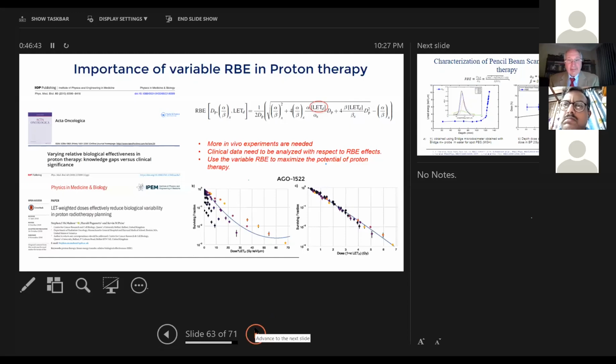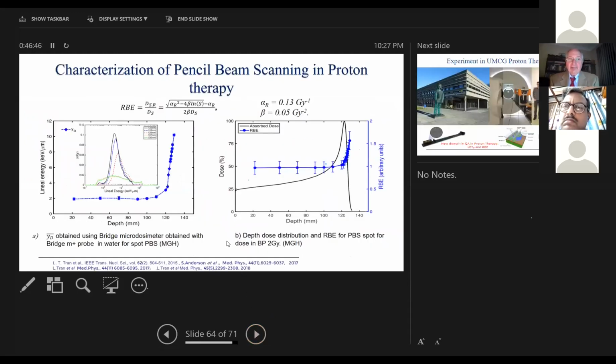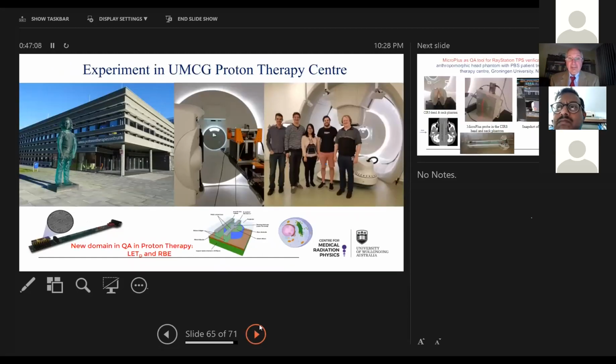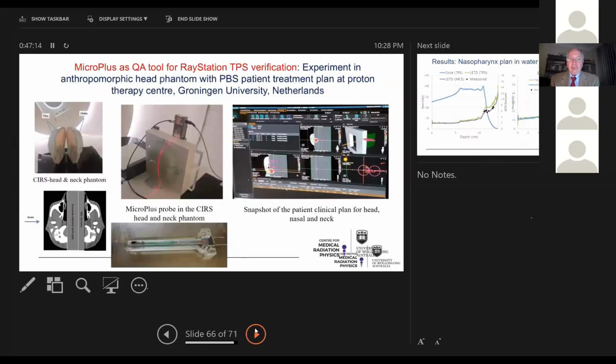So we developed such detectors, and we demonstrated that we can measure dose average linear energy, which increases essentially at the distal part of the Bragg peak, where it is not correct to use the 1.1 RBE in proton therapy. We demonstrated you need to use 1.7 for the last 5-6 millimeters. Currently it's implemented in practice, and in the Groningen Proton Therapy Center we introduced a new quality assurance for RBE in proton therapy.